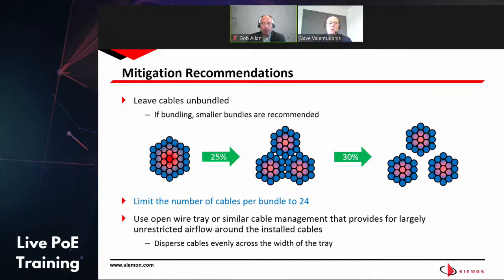What we typically recommend is limit those cable bundles to 24 as they come back in. Why? Because that aligns with your patch panel counts—it's an easy number to remember. And as you'll see on one of our cable dissipation tables, it matches the number for what you can do with category 6A shielded cabling, the allowable cable bundle sizes.